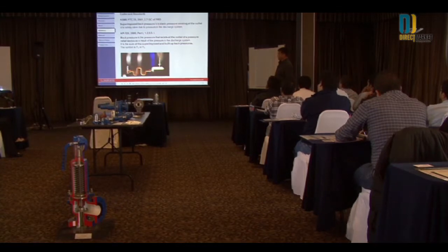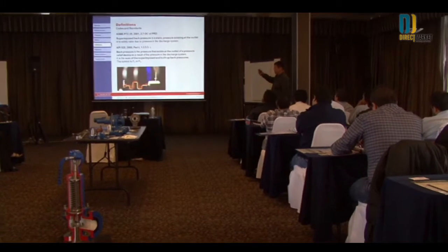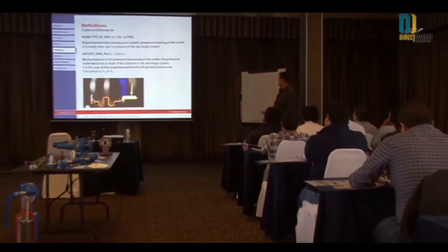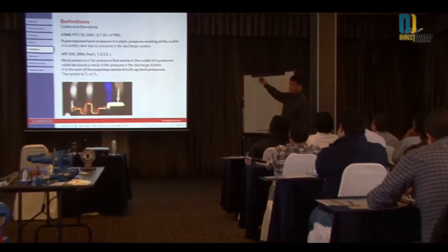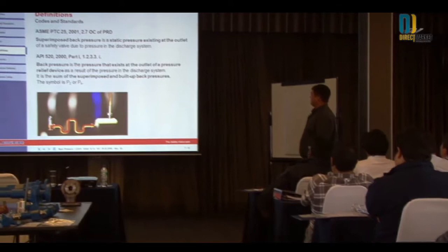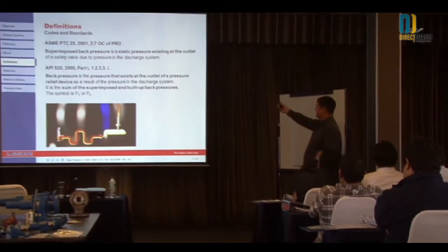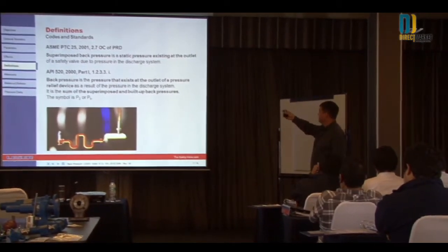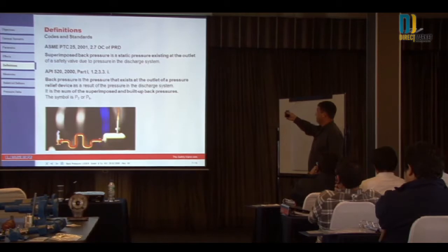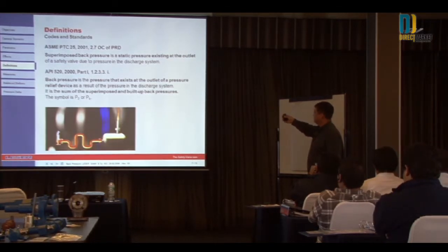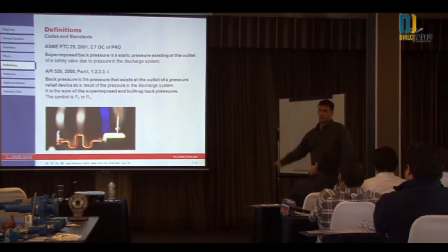ASME and API recognize that back pressure has these influences and make a statement about it. The ASME states: superimposed back pressure is a static pressure existing at the outlet of the safety valve due to pressure in the discharge system.